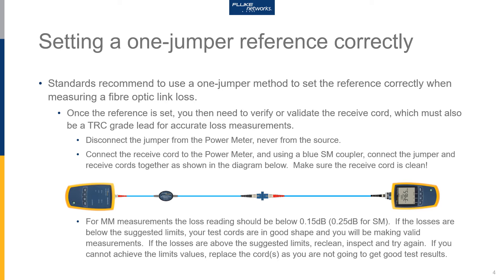Disconnect the jumper cord from the power meter — never break at the source connection. If you break the connection at the source, you have to go and set the reference again. Connect the receive cord to the power meter, then connect the jumper and the receive cords together as shown in the diagram. We're using a blue single mode adapter, as we find single mode adapters lead to a better overall reference result.